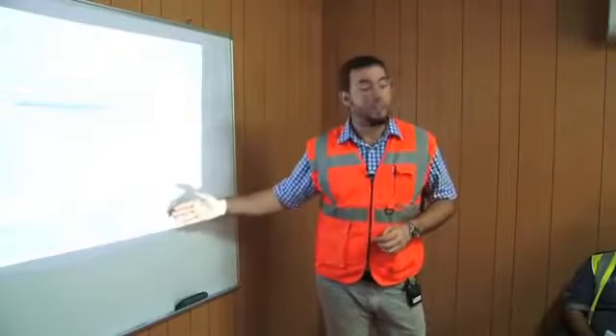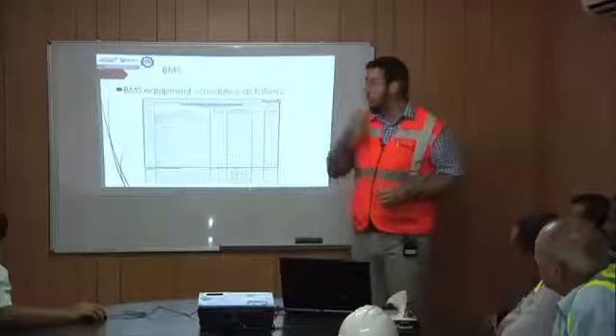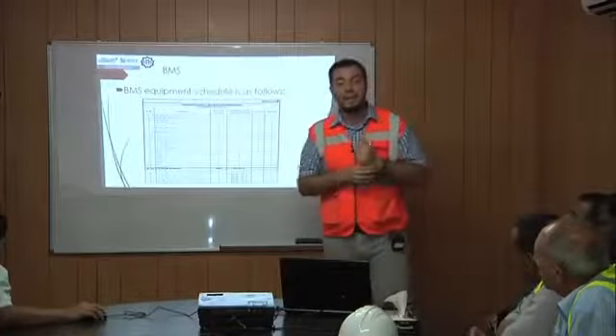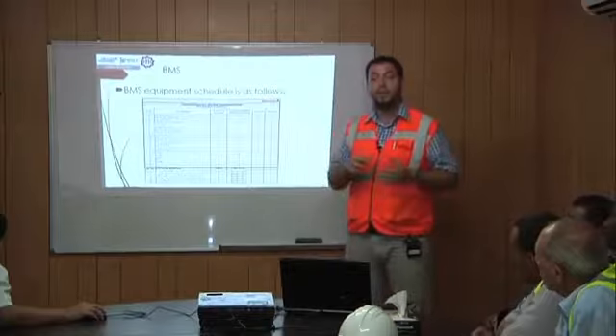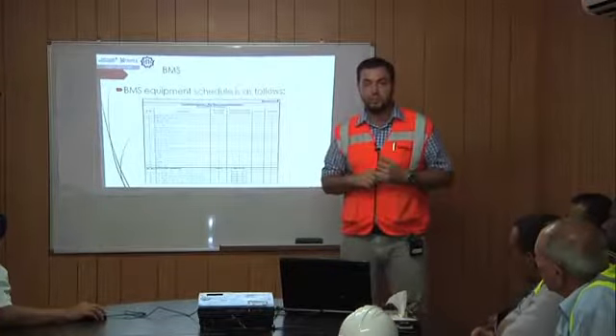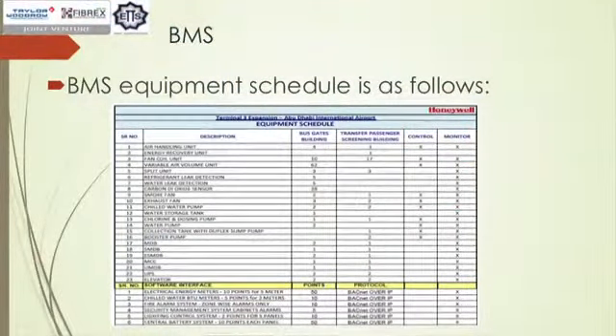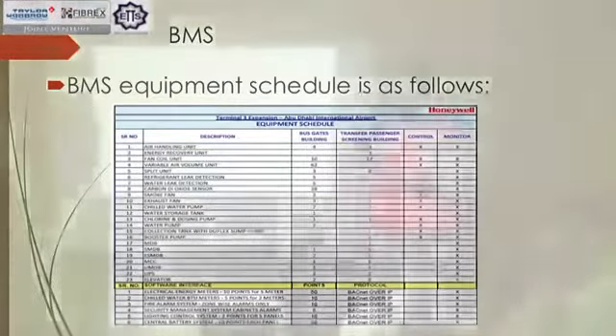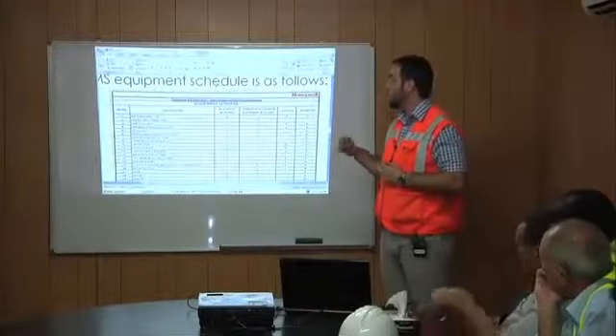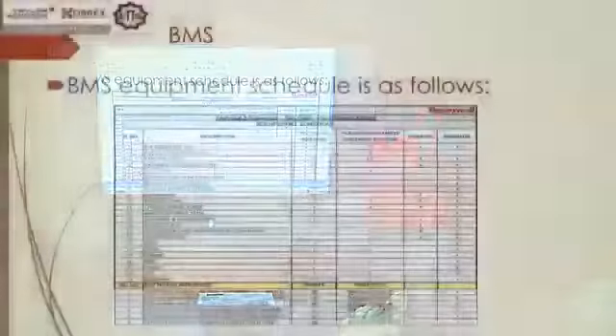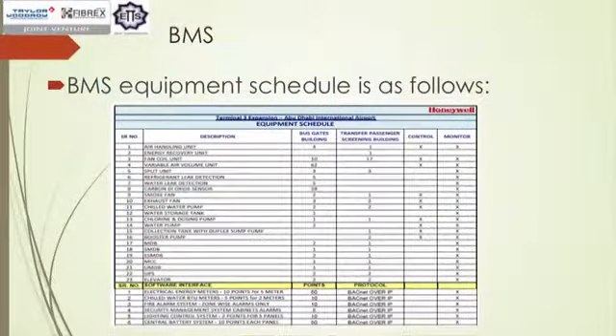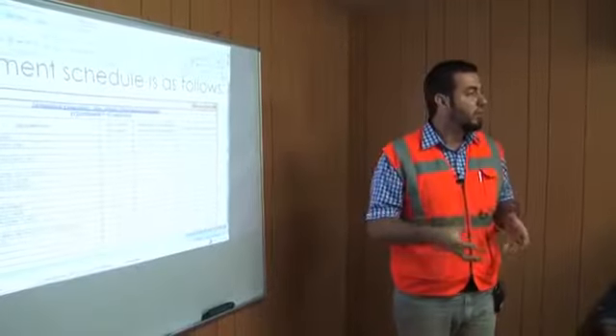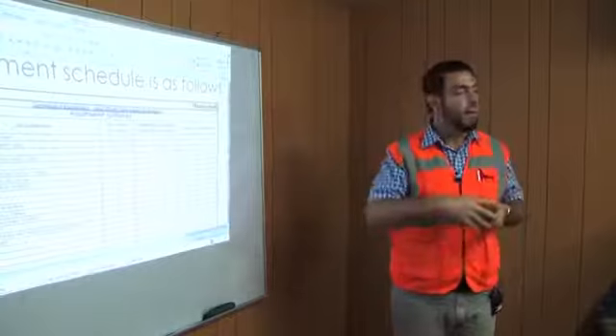We have a lot of machines that we are just monitoring. Through BMS, we have gas leak detection for the split units that are located for the communication rooms. We have all the DBs, all the SMDBs, they have monitoring. Because of the air handling units, energy recovery units, variable air volumes. The system for the air handling is high pressure variable air volume terminals we have in every single branch.